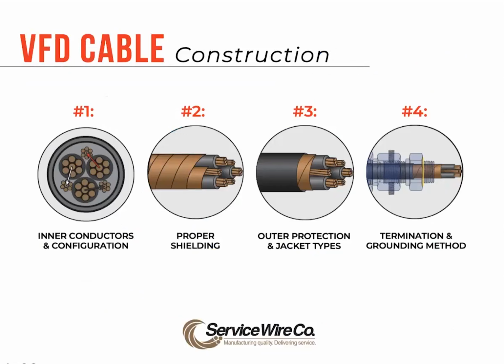Now for an understanding of VFD cable in automotive plants, it is important to note that Service Wire consists of cable, self-terminating connectors, and termination kits. The cable is insulated with heat and moisture resistant XLPE and covered with a helically applied copper tape shield and overall black PVC, CPE, or low smoke zero halogen jacket. We offer connectors for direct wire, liquid tight, NPT conduit, and interlocked armor installations. The termination kits should be used in tandem with the connectors to ensure 360-degree termination, creating the lowest impedance path.